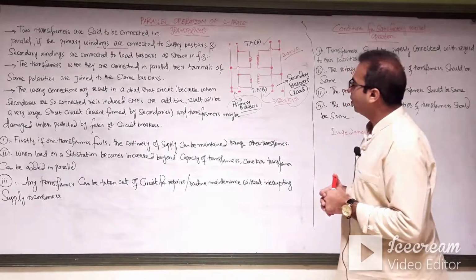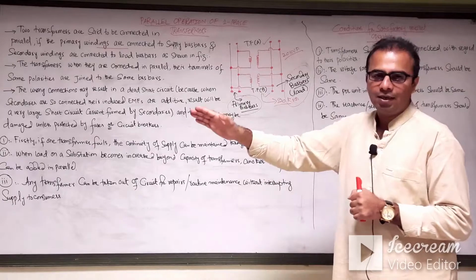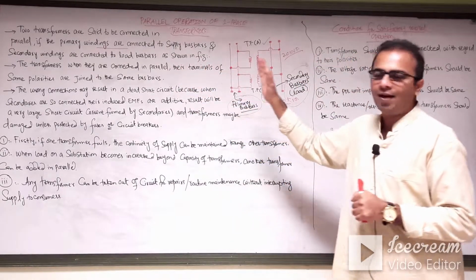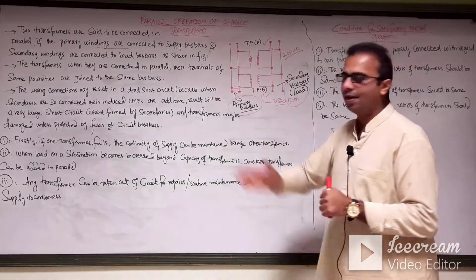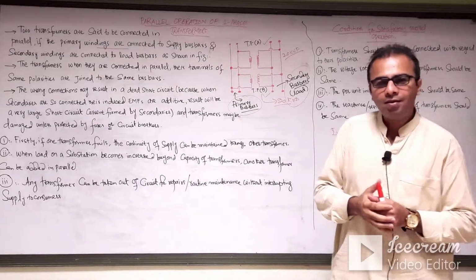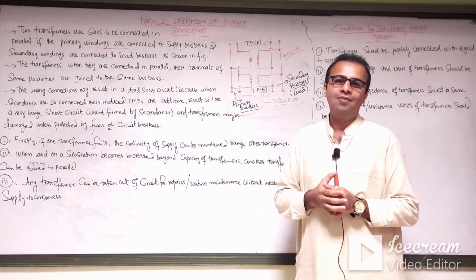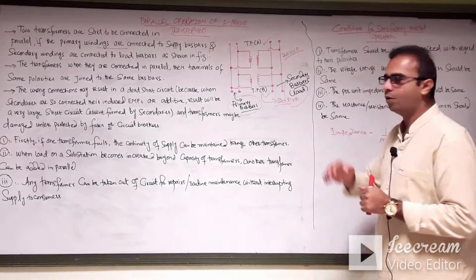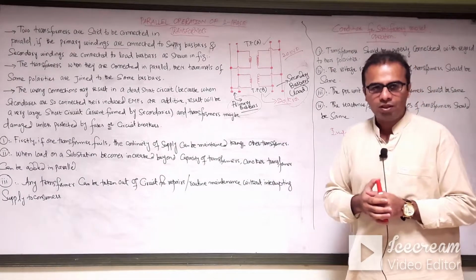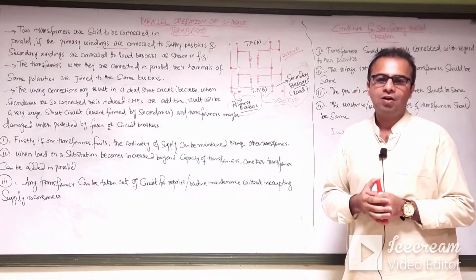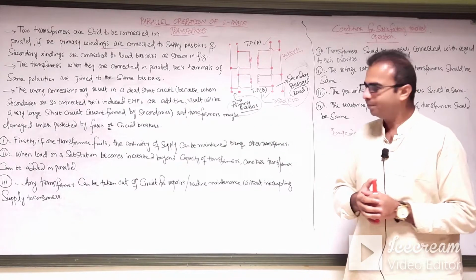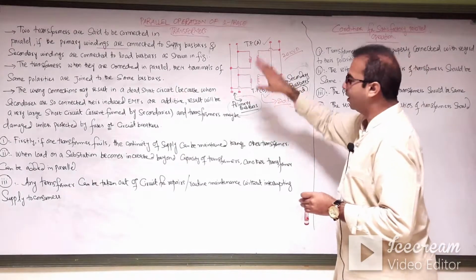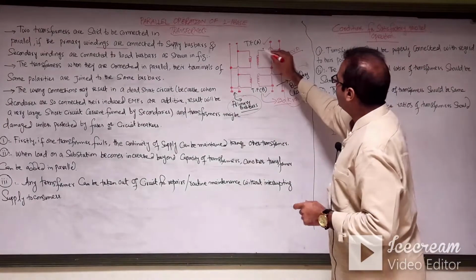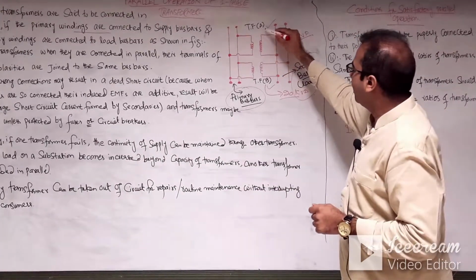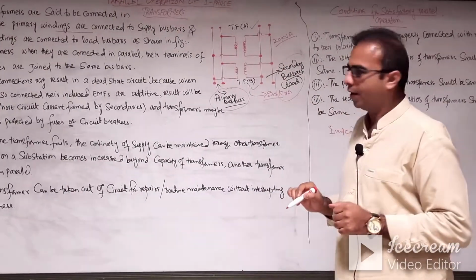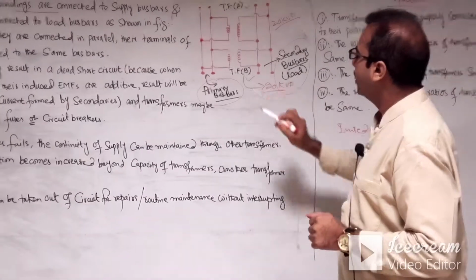Two transformers are said to be connected in parallel if the primary windings are connected with the supply bus bars and both transformers' secondary windings are connected with the load bus bars. So this will be called the parallel operation of single phase transformers. Now consider this figure. These are the two transformers, transformer A and transformer B. Both are connected in parallel.